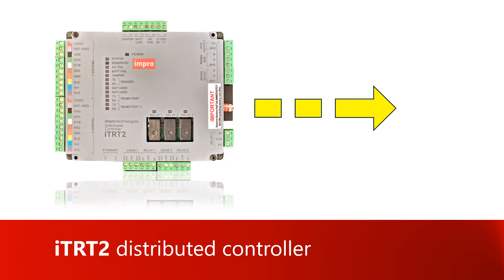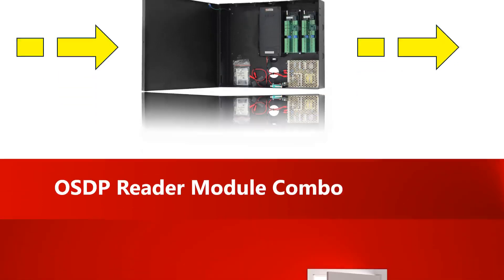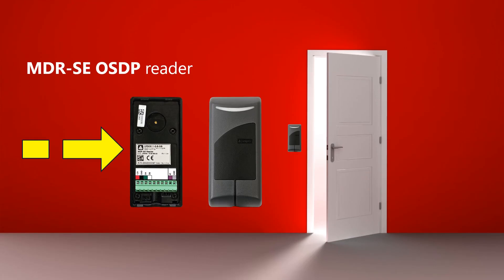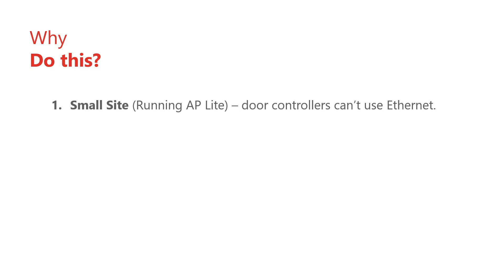This video will show you how to connect a master iTRT2 distributed controller to a slave cluster controller OSDP reader module combo and then connect that to an MDRSE OSDP reader. There are two reasons why you may need to do this. The first reason is AP Lite doesn't support Ethernet door controllers. If you require an additional door controller at an AP Lite installation, it must be connected to the AP Lite master controller via RS485.